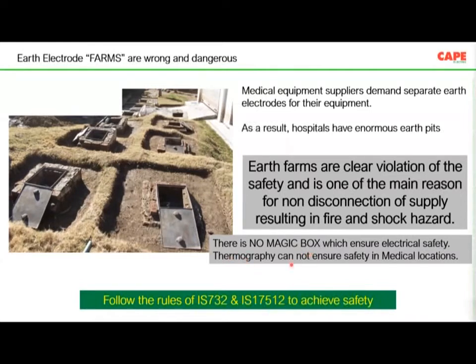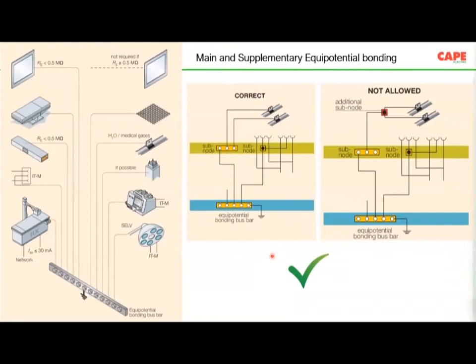Also, a lot of hospitals are doing thermography in the final wirings to ensure electrical safety. But in the last slide, I will explain what kind of testing is required. Thermography, unfortunately, is not recognized for low voltage electrical installations as a reliable testing measure. Then what do we need for earthing? As I am showing in this picture, the correct way of earthing is called main equipotential bonding and supplementary equipotential bonding.